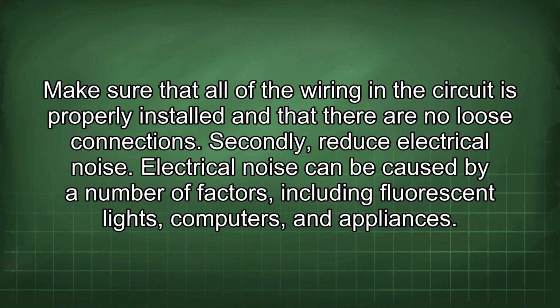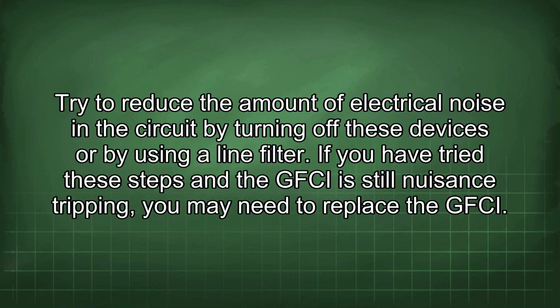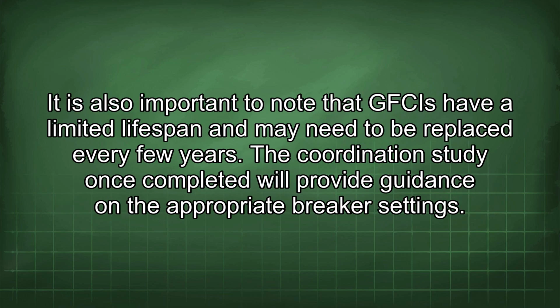Secondly, reduce electrical noise. Electrical noise can be caused by a number of factors, including fluorescent lights, computers, and appliances. Try to reduce the amount of electrical noise in the circuit by turning off these devices or by using a line filter. If you have tried these steps and the GFCI is still nuisance tripping, you may need to replace the GFCI. It is also important to note that GFCIs have a limited lifespan and may need to be replaced every few years.